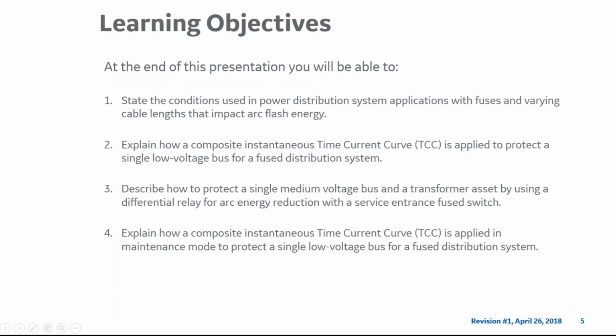Learning objectives. At the end of this presentation, you will be able to, number 1, state the conditions used in power distribution system applications with fuses and varying cable lengths that impact arc flash energy. Number 2, explain how a composite instantaneous time current curve is applied to protect a single low voltage bus for a fused distribution system. Number 3, describe how to protect a single medium voltage bus and a transformer asset by using a differential relay for arc energy reduction with a service entrance fuse switch. And finally, number 4, explain how a composite instantaneous time current curve is applied in maintenance mode to protect a single low voltage bus for a fused distribution system.